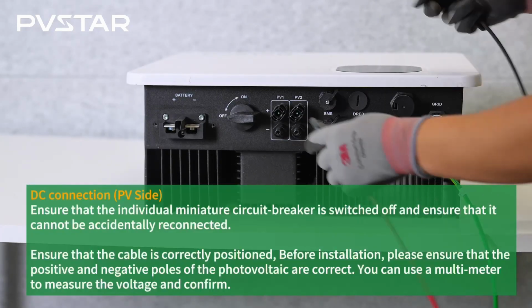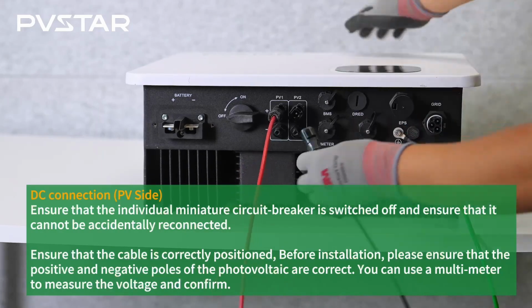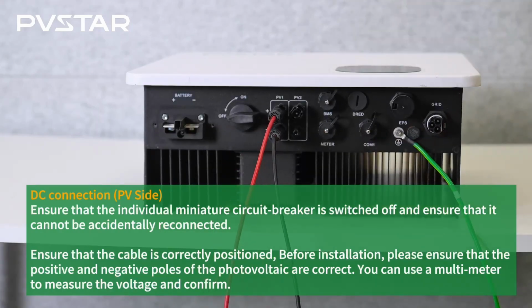In the next step, we will do the DC connection on the PV side. Ensure that the individual miniature circuit breaker is switched off, and ensure that it cannot be accidentally reconnected. Ensure that the cable is correctly positioned. Before installation, please ensure that the positive and negative poles of the photovoltaic are correct. You can use a multimeter to measure the voltage, and confirm.